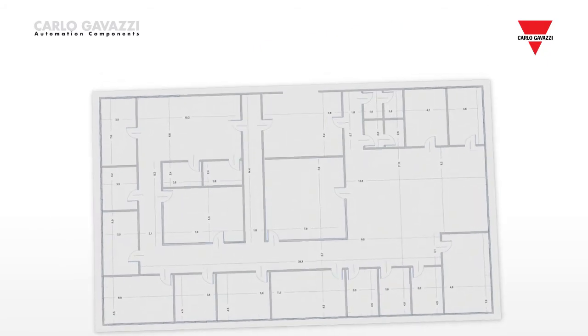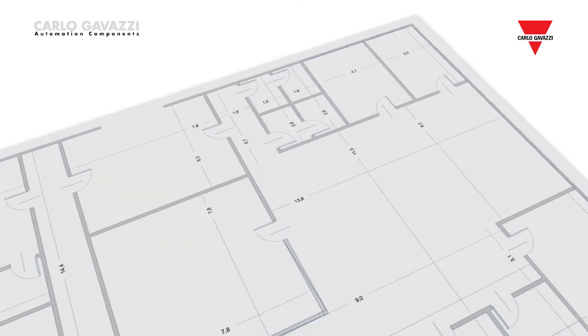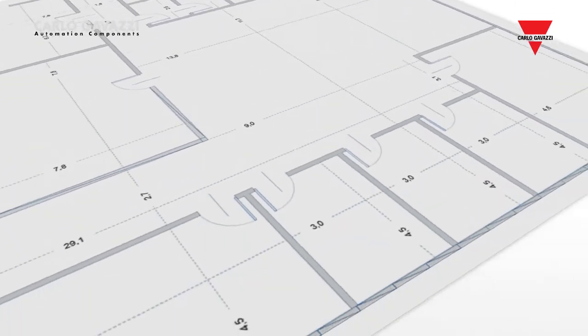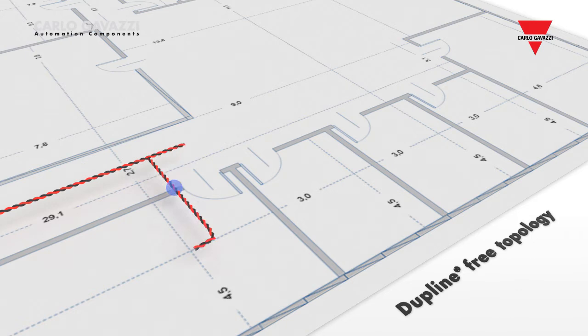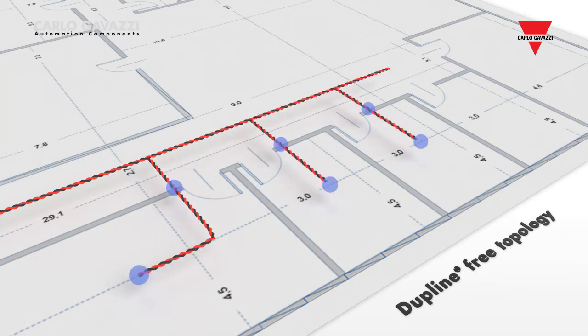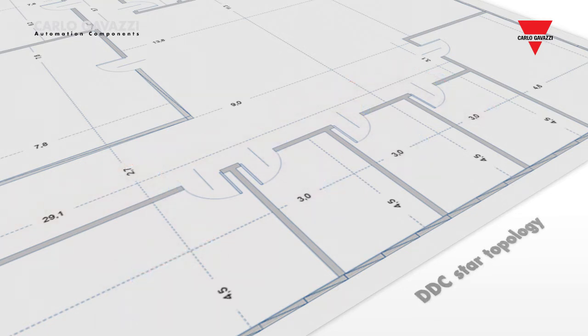Dupline is not based on RS-485 technology, so is not constrained by RS-485 rules. This means completely free topology for the cable installation and no special cable or end-of-line terminations are required.